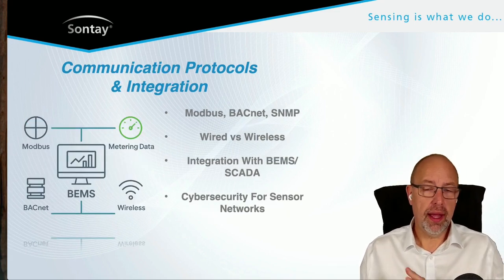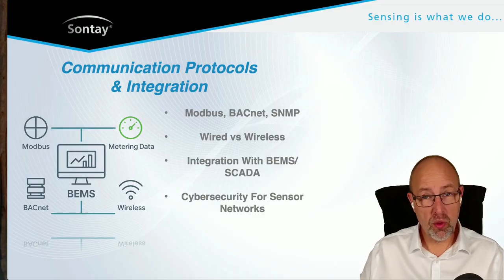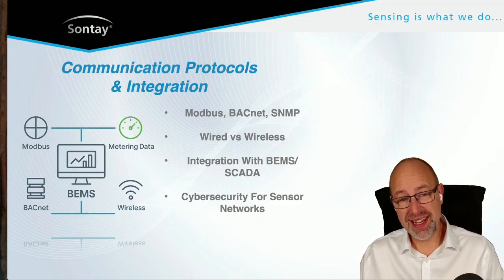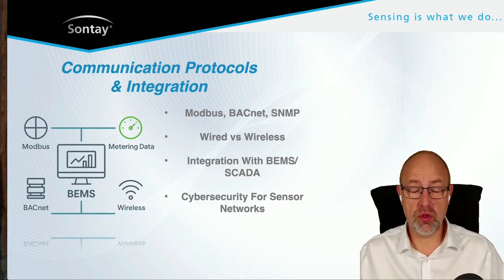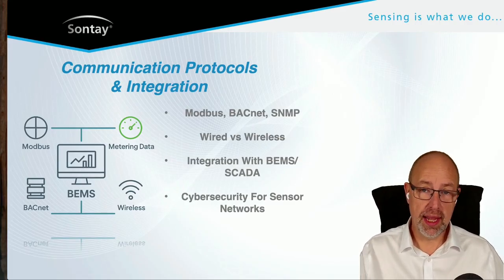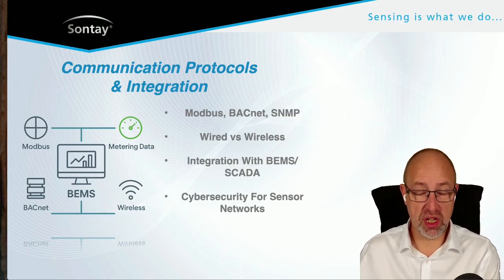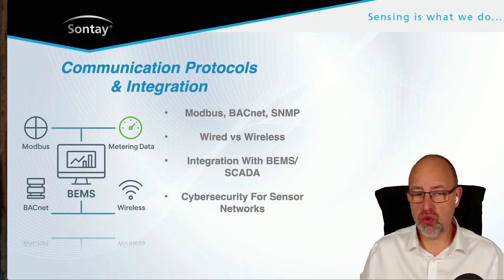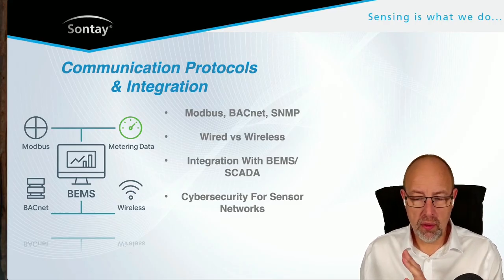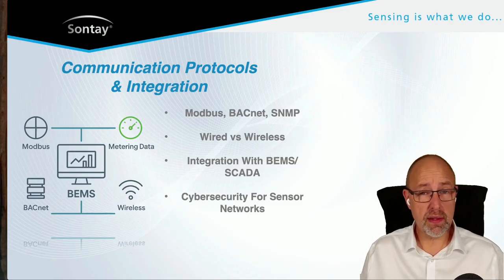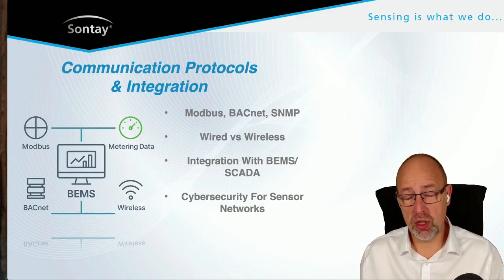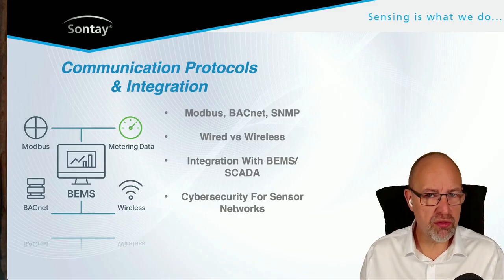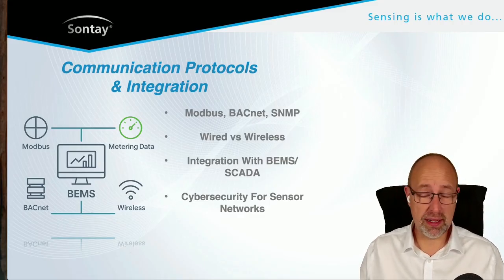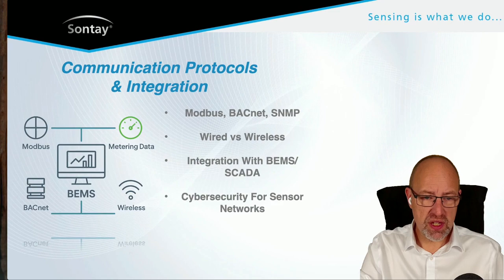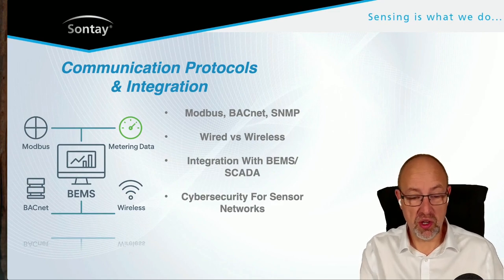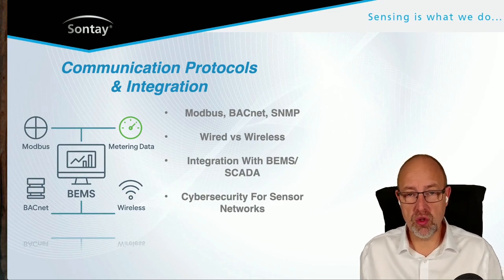As a slight aside, just a little bit about communications protocols and integration. Very often in data centers, we're required to integrate equipment into bus topology networks. There are benefits and drawbacks to doing this. So there's a couple of things that we do. One of these is in terms of these bus communications networks, we will probably look at some metering in a data center, going back to the BEMS. That is required so that obviously we can see where energy is being used in the building.